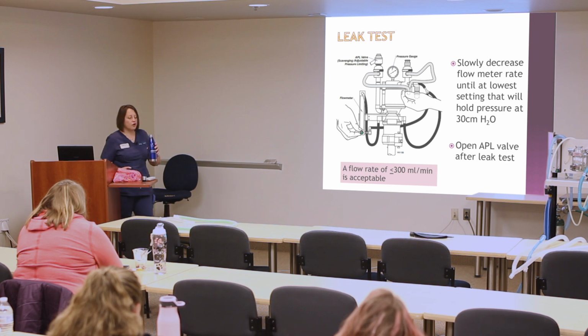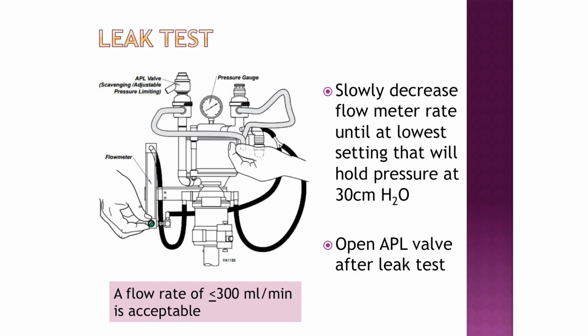And then make sure that you always open the pop-off when you're done checking for leaks. If you want to cheese off the people that you work with, you will leave that shut, and they'll be very mad at you. But flow leaks under 300 milliliters per minute is considered acceptable, and that would be for some of the dinosaurs that are out there, so that 1939 machine or the one that looks like it belongs in somebody's kitchen. It's got a cabinet and all these pretty columns and all that. But for our machines, we're not seeing anywhere near this size of a leak on all of these machines.